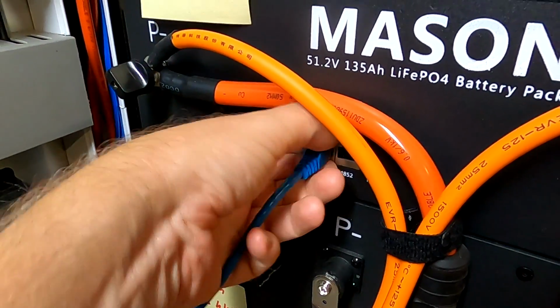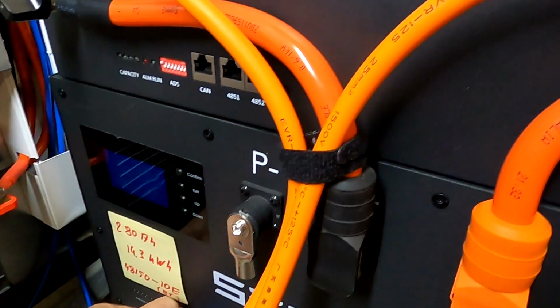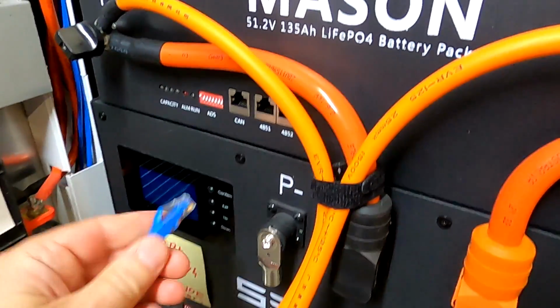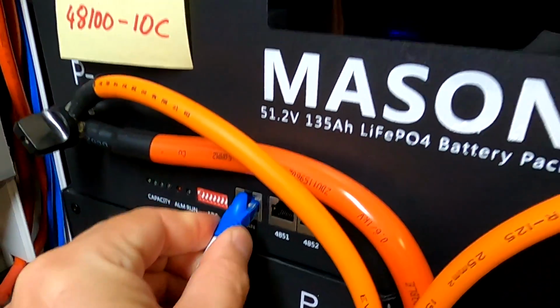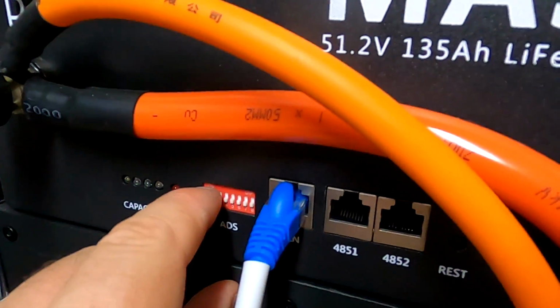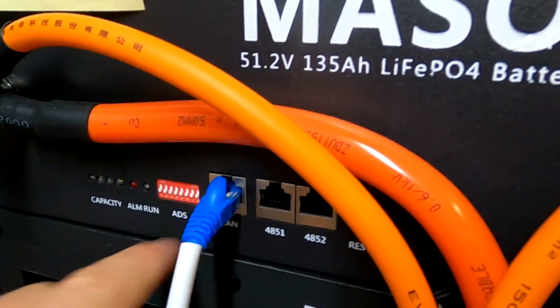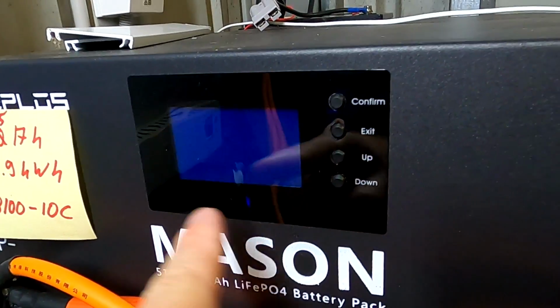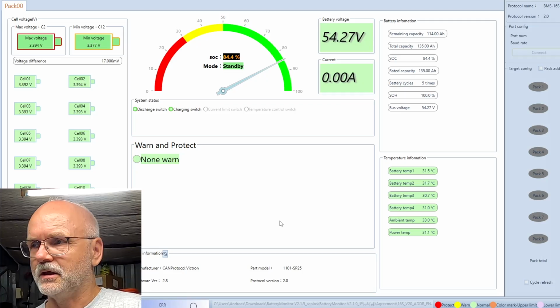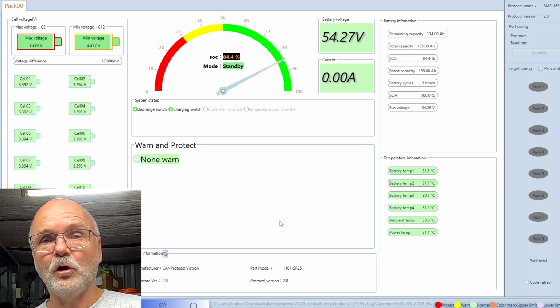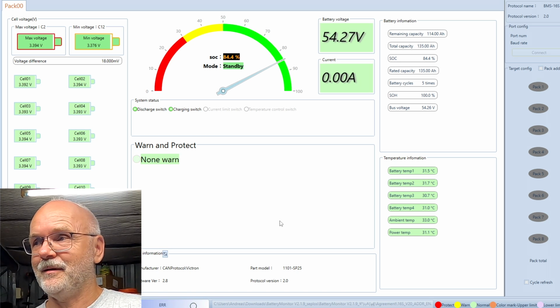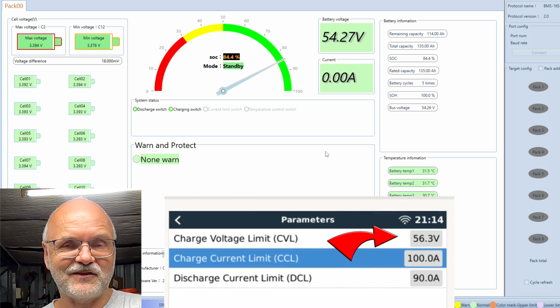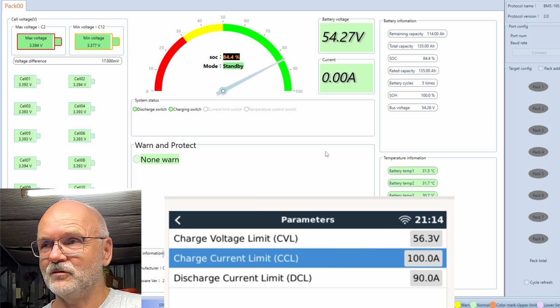So what we're going to do, we disconnect the link to the master and take out the CAN and plug this in directly into our smaller battery and take the dip switch 1 down. So this is now the only BMS connected to the system. So we are now connected via the battery monitor software from the computer to the older BMS from SEPLOS, the 10C BMS. And you can see here in the parameters of the Victron system, the maximum charge voltage has changed to 56.3 volts all of a sudden, right?